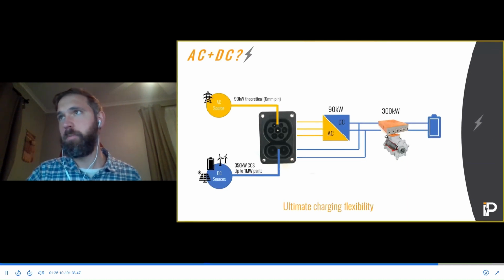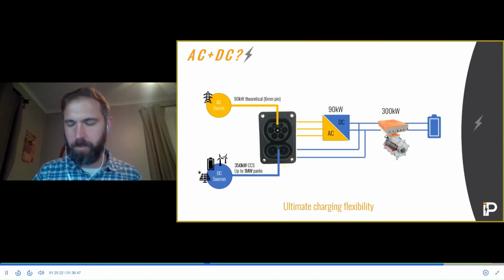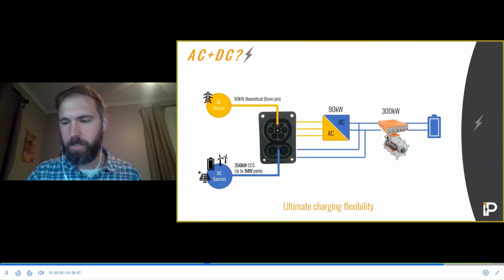I know that, but it's just an option. My focus has been on the DC because the traction drive is going to be rated at a couple hundred kilowatts. If you're only operating at the standard Type 2, 43 kilowatts or 52 kilowatts in the US at 480 volts, you're not operating the drivetrain electronics to their full potential. If you've got half a megawatt worth of power electronics and you're charging at 40 kilowatts, its efficiency is not as high as it could be because the electronics want to push harder.